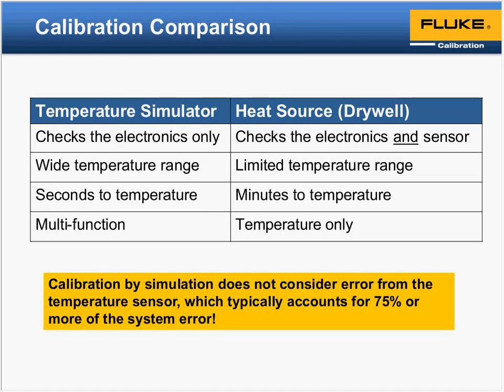When you're doing a calibration comparison, I guess there's a few different methods. So basically in the slide, we're looking at temperature simulation versus using a heat source. So in the simulator side, you're basically only checking the electronics of the readout piece that you're using. When you're using a simulator, there are some advantages in that you get really quick responses. You're just programming the temperature or the resistance, and then hit go, and you're basically taking a reading.